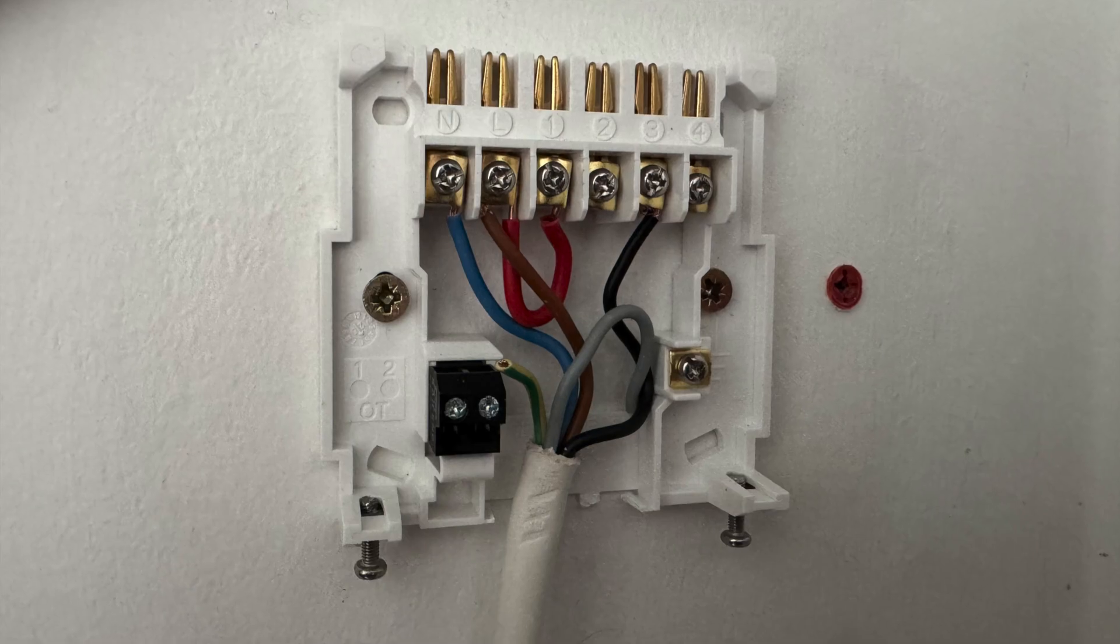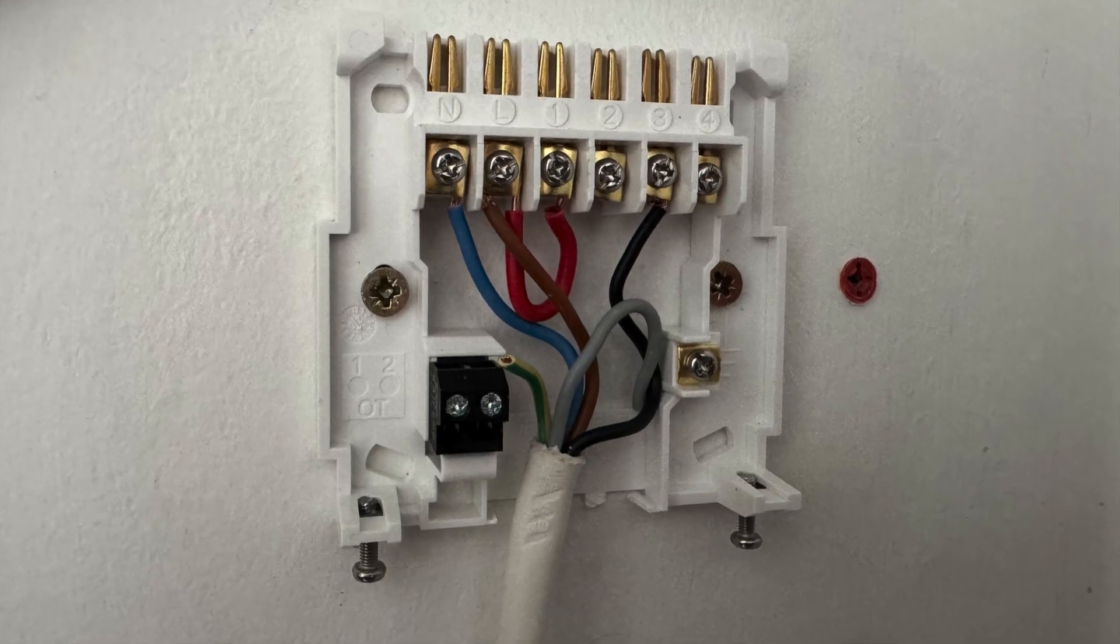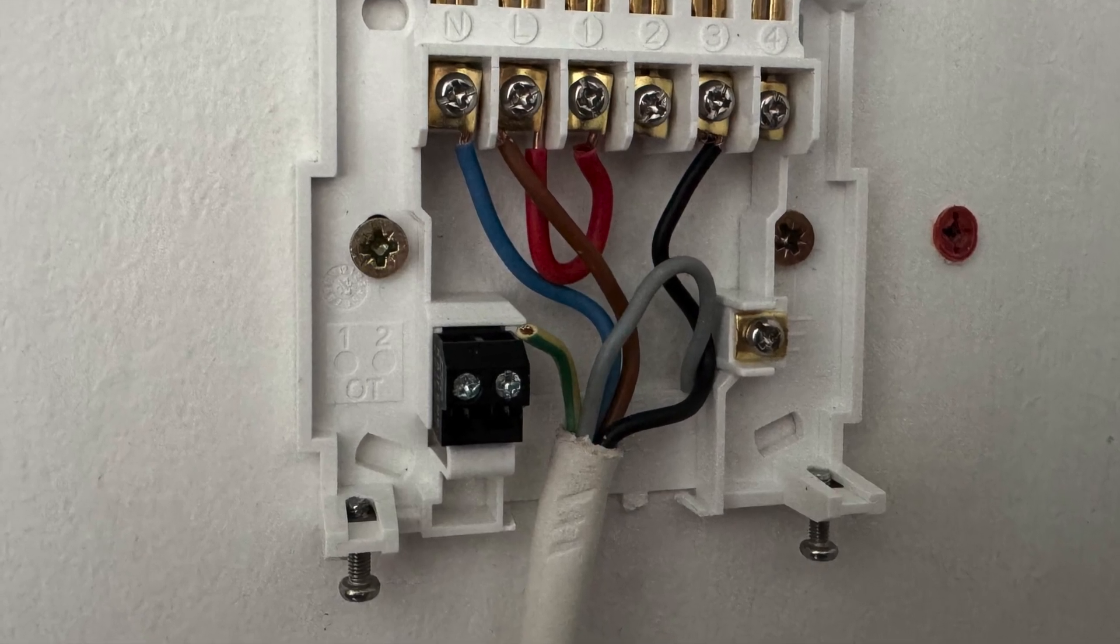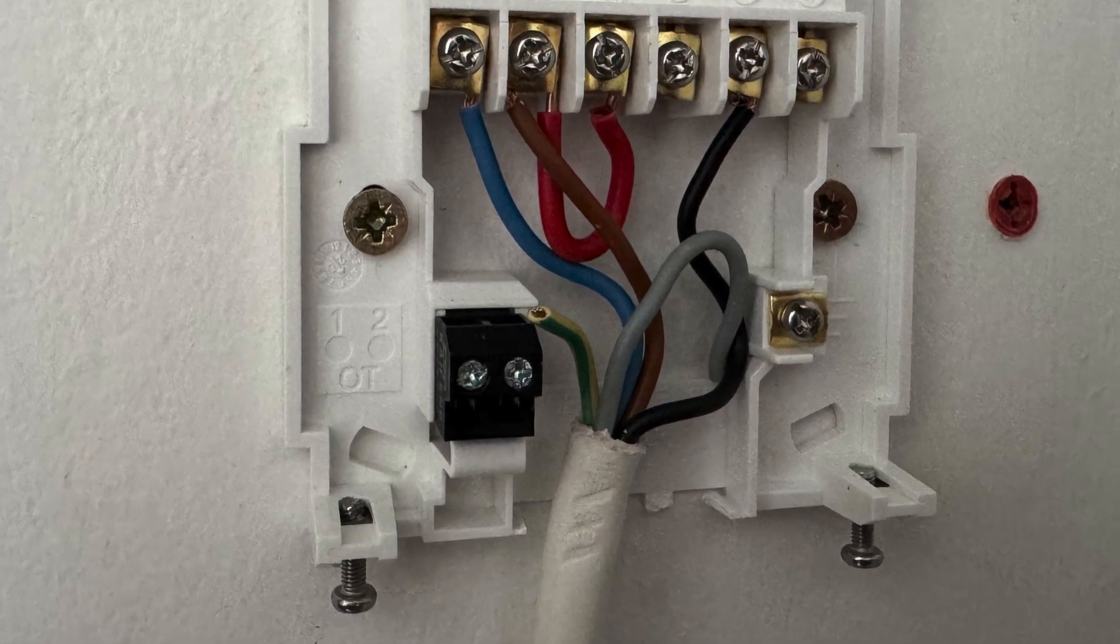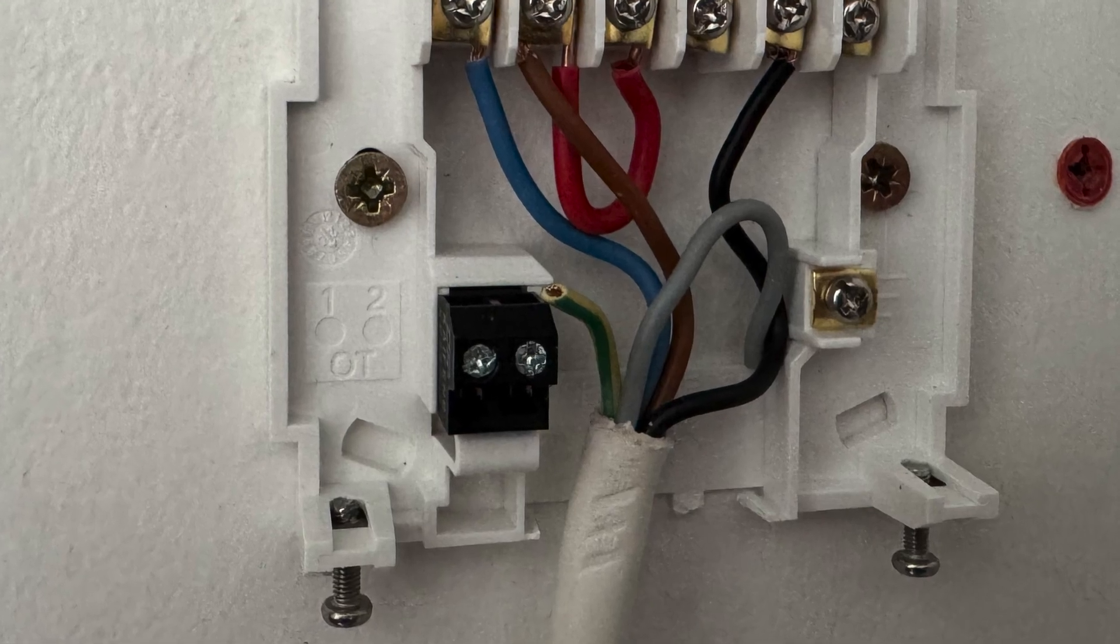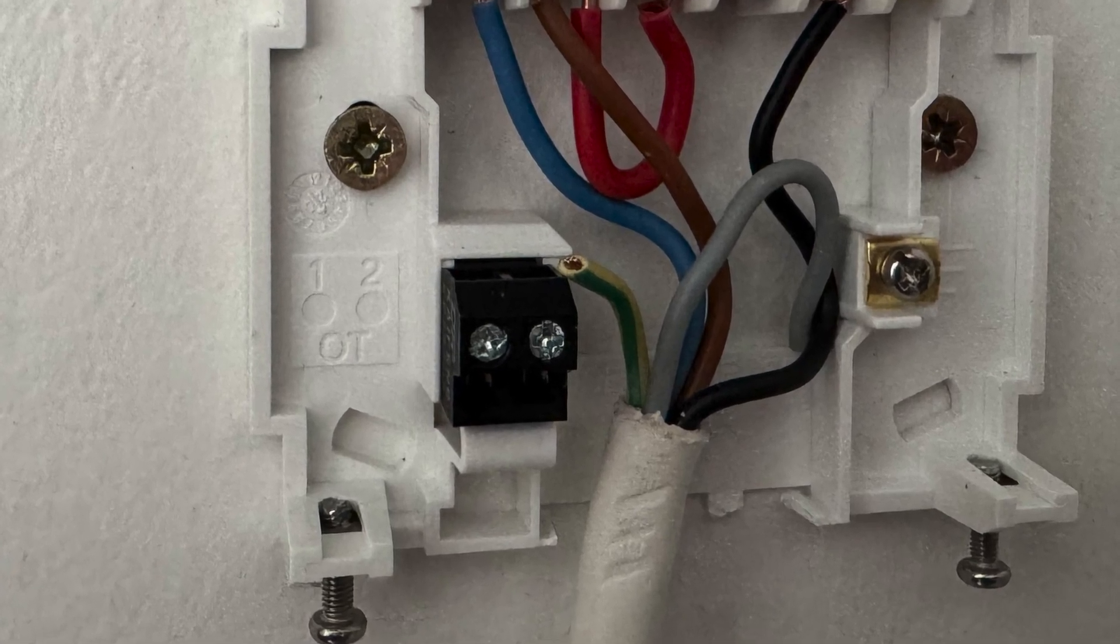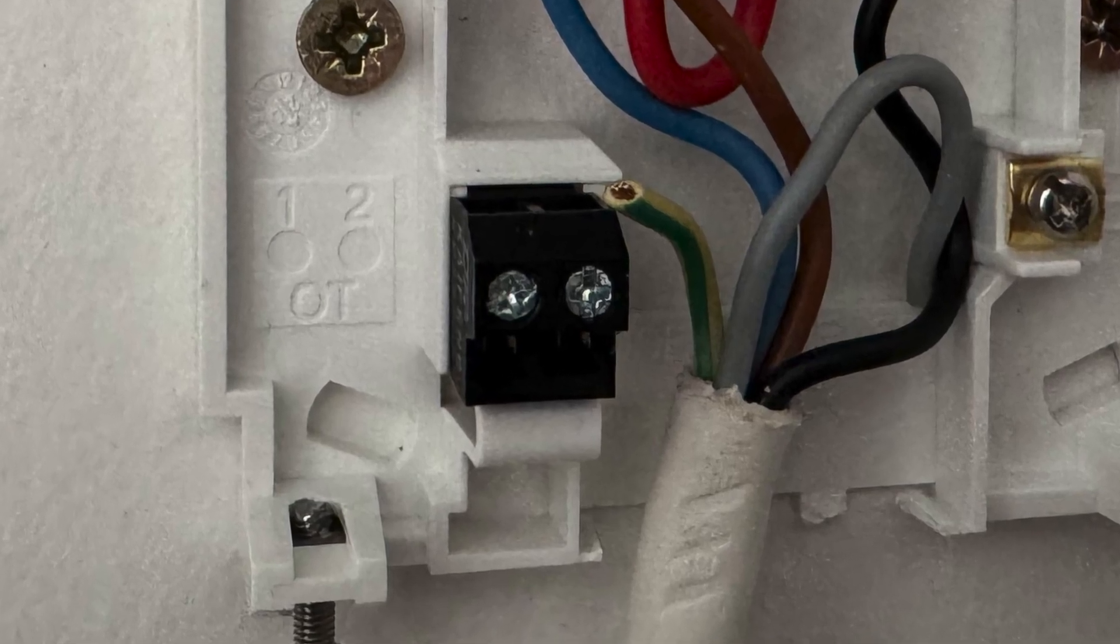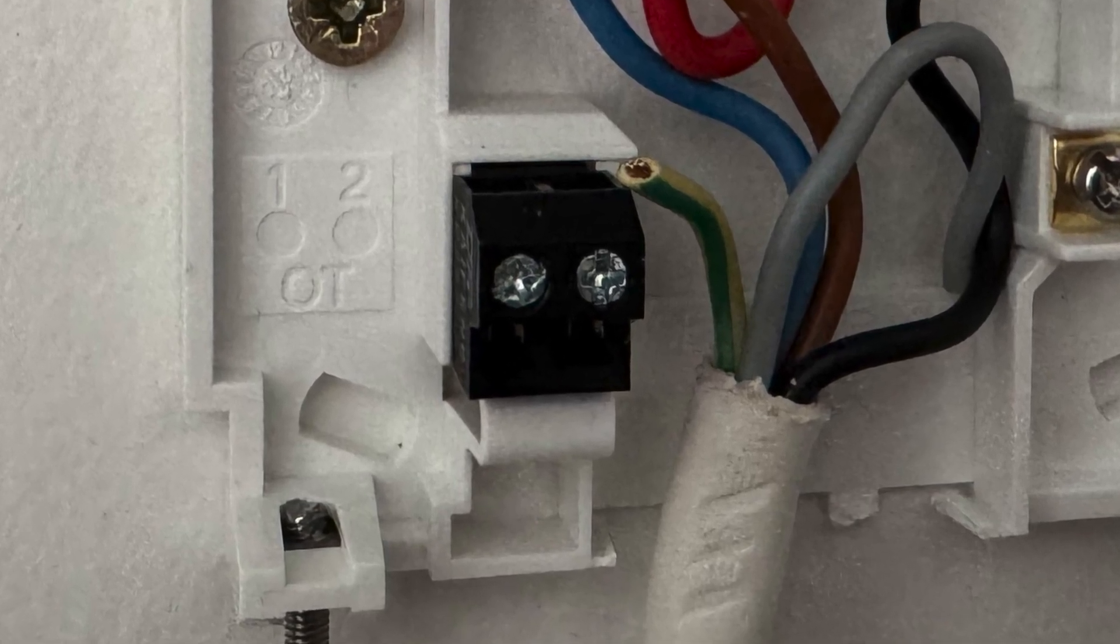Now just a word of warning, this thermostat is OpenTherm compatible. So what that means is do not put 230 volts AC to this little black connector here. Because if you do you will blow up your thermostat. So you have been warned.